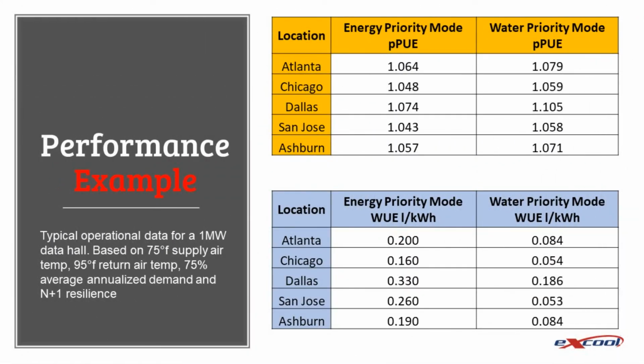When it comes to performance, the Excool Zero is world-beating, offering the option to operate in energy priority mode that demonstrates the lowest best-in-class partial PUE, or operating in water priority mode, where the unit would feature the lowest WUE values of any indirect evaporative data center cooling solution on the market today.